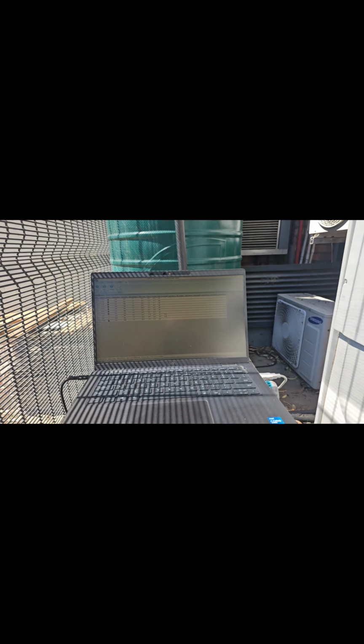All right. Okay guys, so to conclude that assessment, what we found was compressor 1, the digital scroll compressor on the slave module, that compressor was bypassing internally.